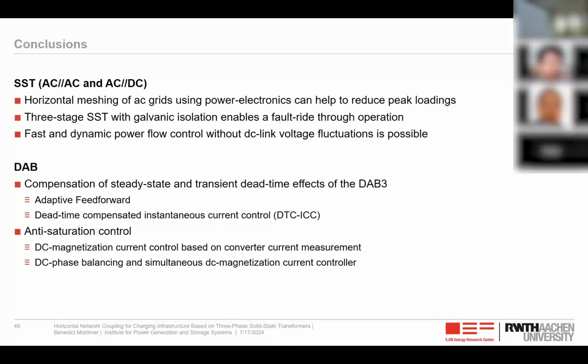And for the DAB, we saw that we can compensate the steady state and transient dead time of the DAB using this adaptive feed forward and this novel dead time compensated instantaneous current control. And also we can utilize the anti-saturation control based on the converter current measurements. So this is in our case also possible. And we can also achieve the DC phase balancing.